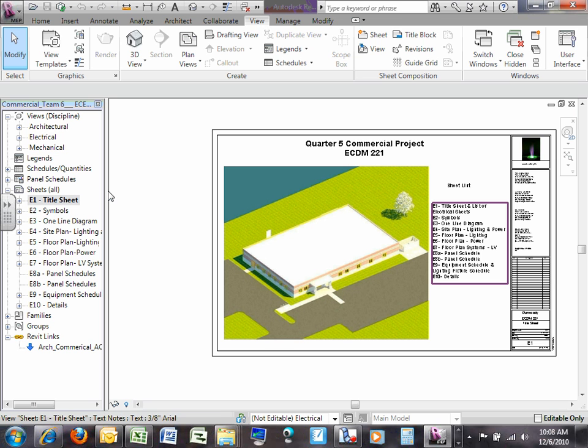Anyway, if you guys read through it, I want to emphasize item D now. We're going to have the following panels. Look at the panels: first the main, and from the main I feed the lighting panel, receptacle panel, these are separate standalone panels, UPS and associated 208/120 panel, air handling unit feed from it, condensing unit, boiler pump 1 and 2, automatic transfer switch for the generator, and an additional device for future lighting panel, all the way to page 12, which is a future device for future equipment.